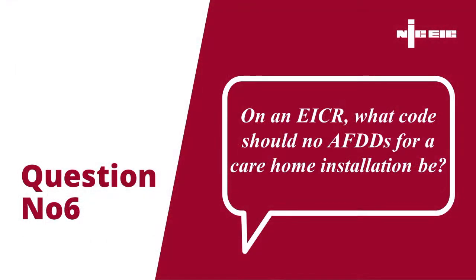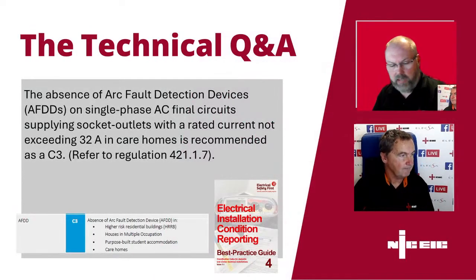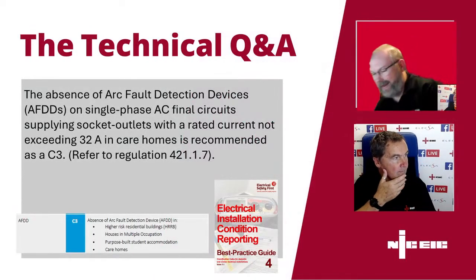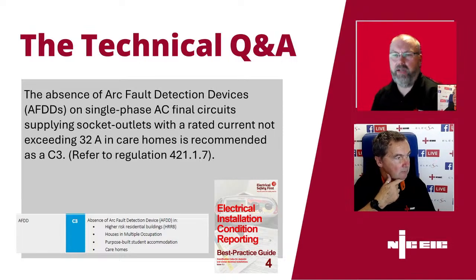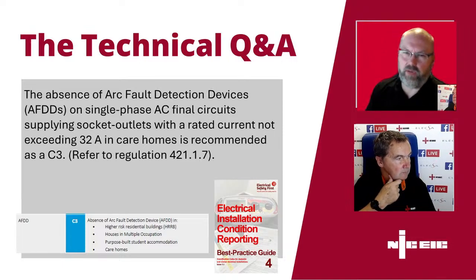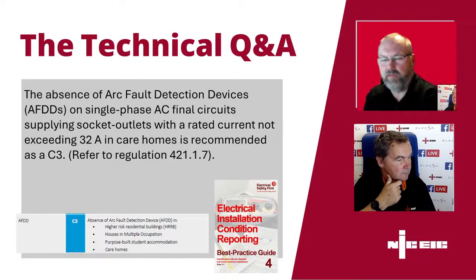We've got a question that's come in, so I'll ask this before we go to the final ones from the field. On an EICR, what code should no AFDDs for a care home installation be? What's our thoughts on that, Craig? Generally it would be a C3, because it would be required if installing now, but not necessarily required at the time of install - so a C3, it's non-compliant with the current edition of the regulations.